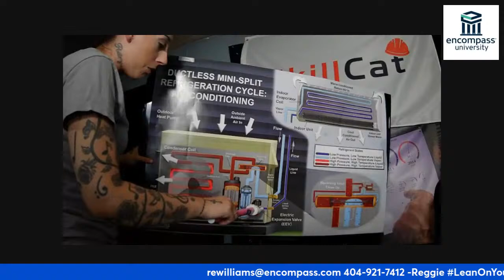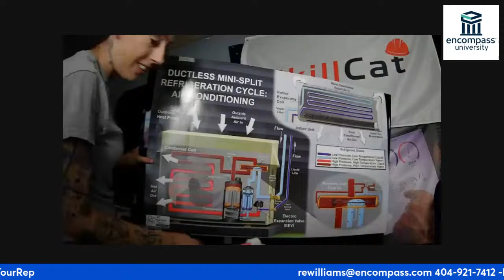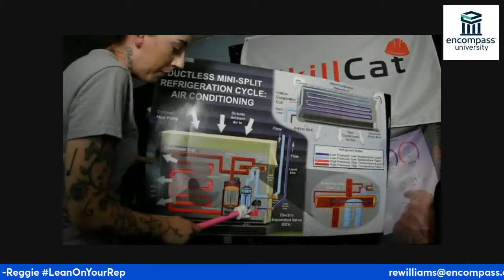Now, when we go through our metering device, and in this case, it's an EEV because it's a mini split, our metering device knows exactly how much refrigerant to meter at any given time. So we have our full charge of refrigerant going throughout the whole system, but after the metering device, we do not. So as we come back from the compressor, we'll go this way into the EEV, we have all of this red liquid, all of this hot liquid. And that's going to hit the EEV, and the EEV is going to say, no, we need low pressure liquid, and we need this much.